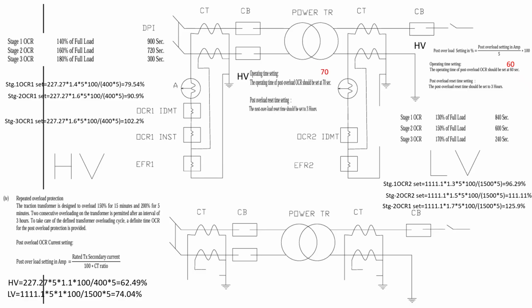Convert it to the CT secondary, that is 1500 by 5, and it is set to 100%. So 100% means 1, it is multiplied by 1, and then convert it to percentage. Full load current is 5, and how much percent of this 5 is the current, that is 100 by 5, so it is 74.04%.